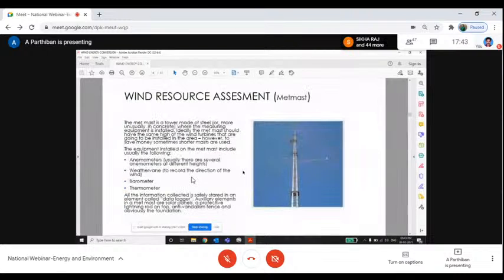So this is the met mast, which will have sensors at different heights. For example, if we need to install a 120 meter tower, then the met mast also needs to be 120 meters. These sensors will be at 120 meters, 110, 100 meters. There will be 4 types of sensors. One is the anemometer, another is the wind vane, the third is the barometer, and then the thermometer. So these 4 things. One is the anemometer.